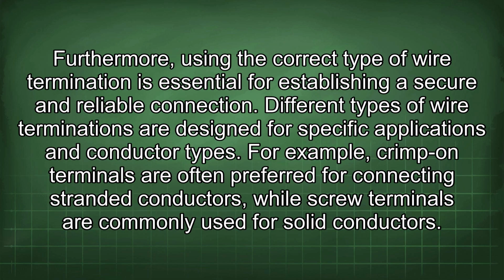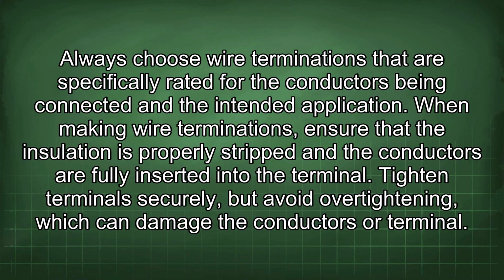Furthermore, using the correct type of wire termination is essential for establishing a secure and reliable connection. Different types of wire terminations are designed for specific applications and conductor types. For example, crimp-on terminals are often preferred for connecting stranded conductors, while screw terminals are commonly used for solid conductors. Always choose wire terminations that are specifically rated for the conductors being connected and the intended application.